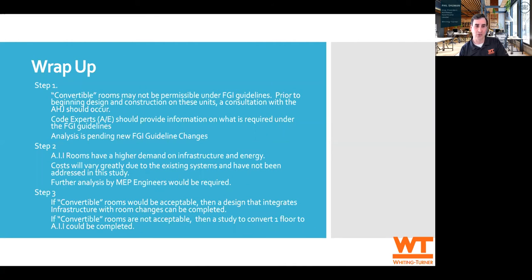And then finally, don't look through a narrow lens at any one renovation. You can't look at it as just one room. You need to look at your infrastructure, because there are potential impacts on the heating and cooling side. Paul was mentioning the O2 lines. One of our clients was bringing in supplemental tankers for O2, but because all of that oxygen was going through one point, it was freezing up the line, and they had to constantly be out there spraying the line with warmer water to warm it up. So speak to those engineers, and look at what it's going to do both from an infrastructure standpoint and to your utility operational budget.